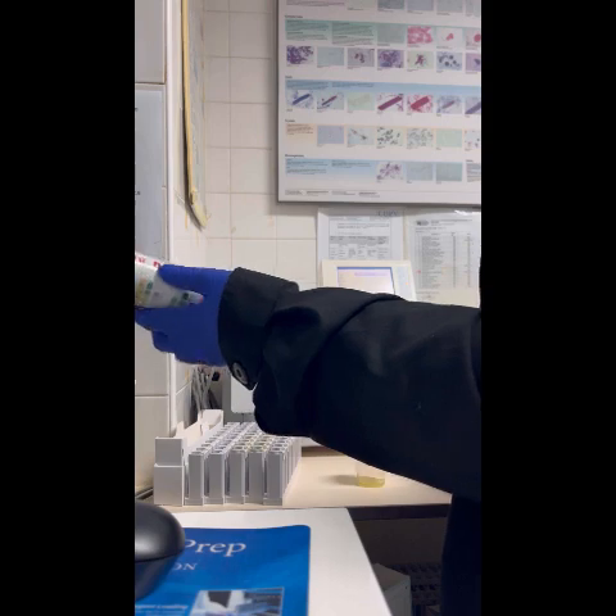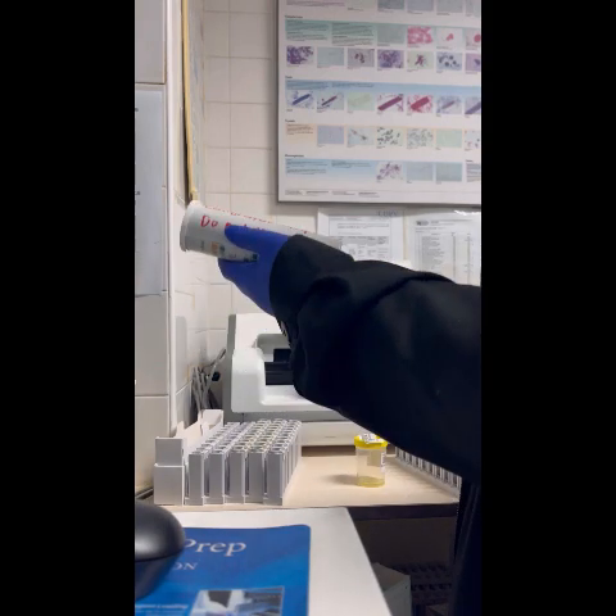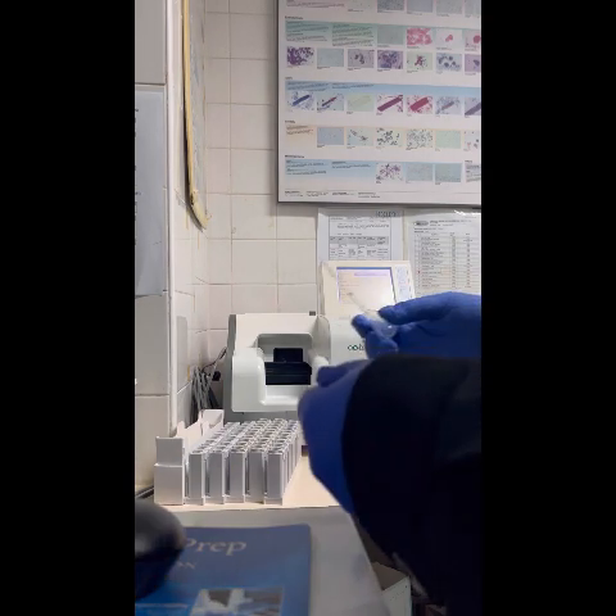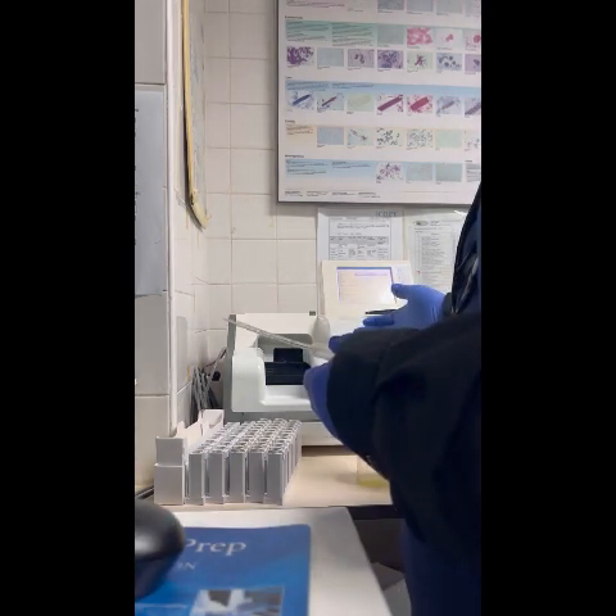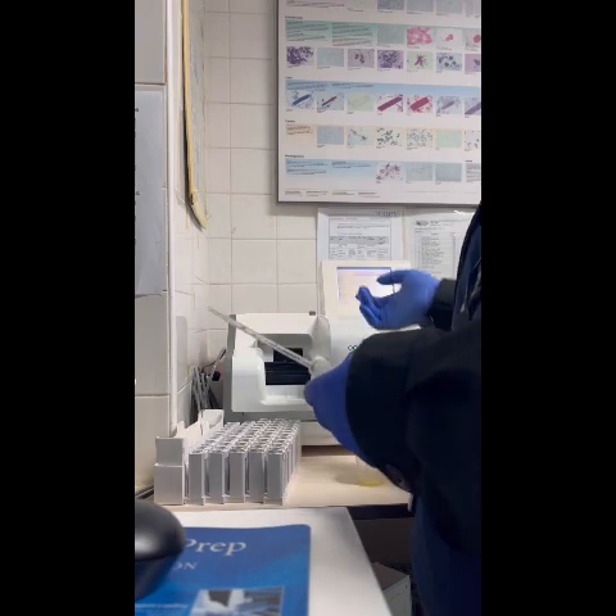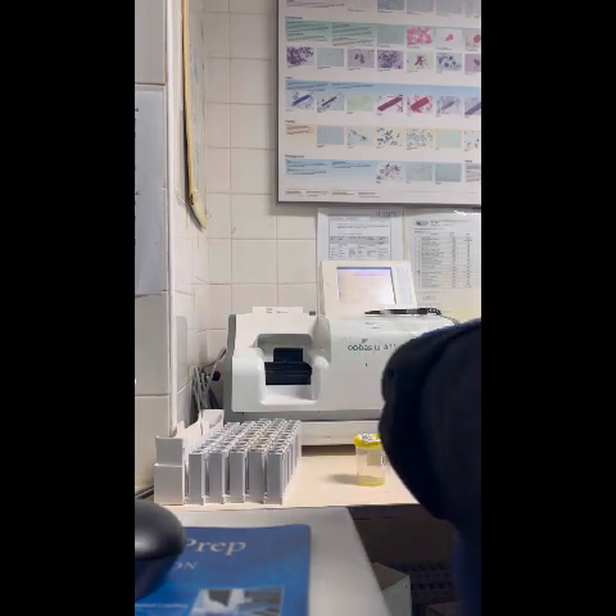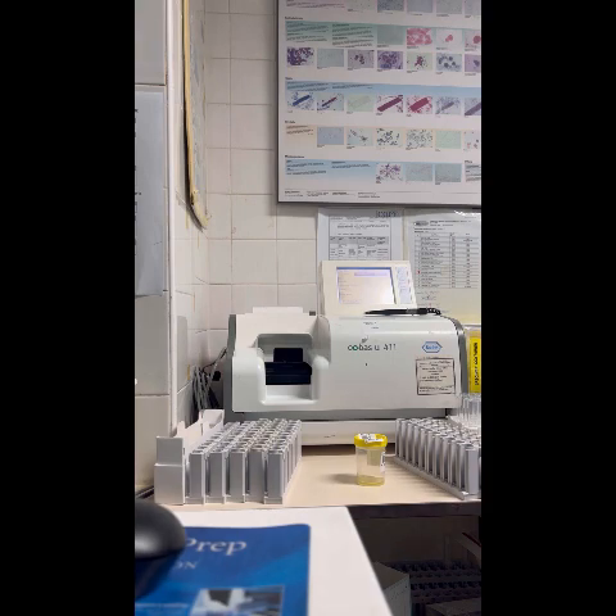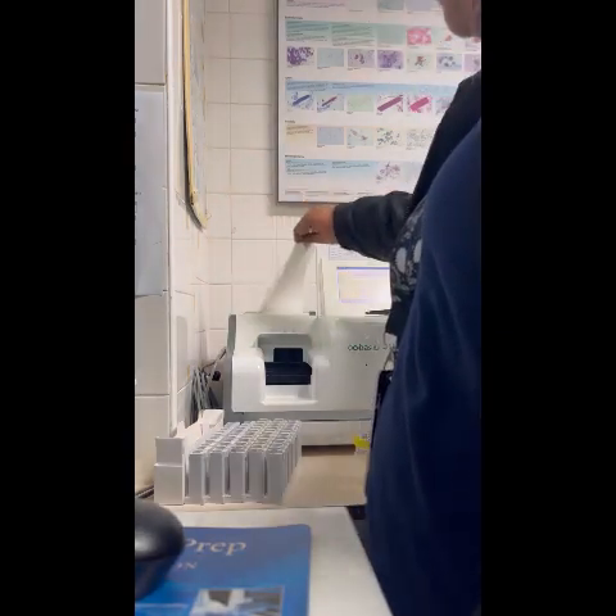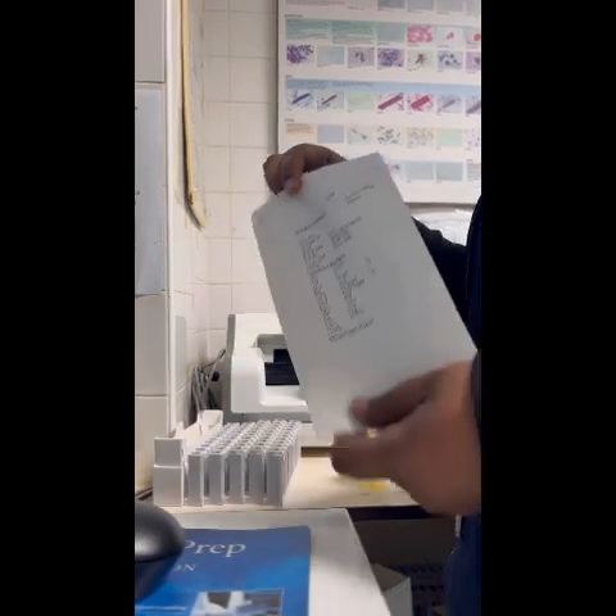For calibration, we have a calibration strip. This we do every month or when needed, or usually when the engineers come and do their own calibration and PPM, then we will have to do calibration and run QC. So after it's done, the results will be automatically printed and we key in the results according to the printed results.